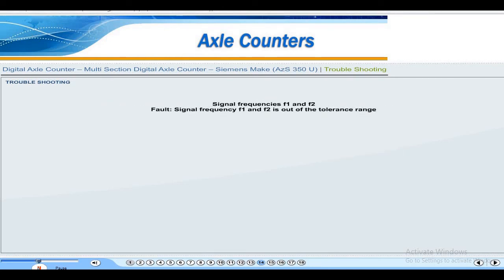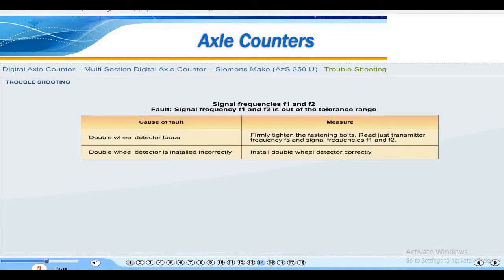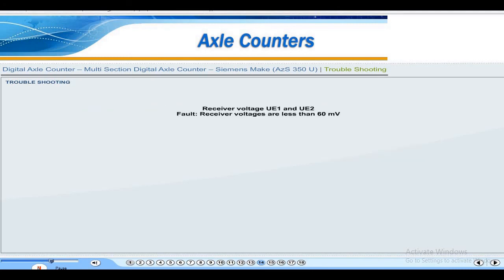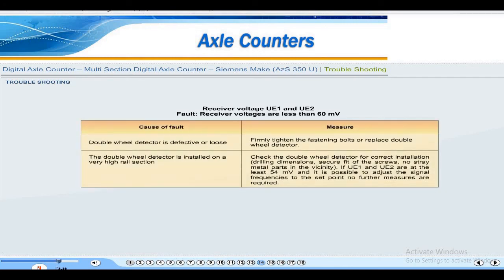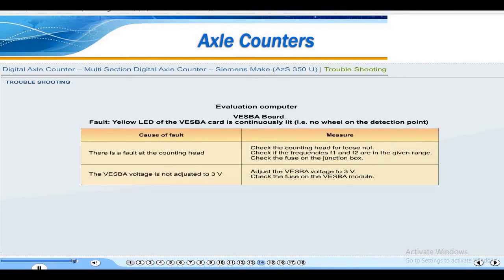Signal frequencies F1 and F2. Fault is signal frequency F1 and F2 is out of the tolerance range. The following table may be referred for troubleshooting. Receiver voltage UE1 and UE2. Fault is receiver voltages are less than 60 millivolt. The following table may be referred for troubleshooting. Evaluation computer. VESBA board. Fault is yellow LED of the VESBA card is continuously lit, that is no wheel on the detection point. The following table may be referred for troubleshooting.